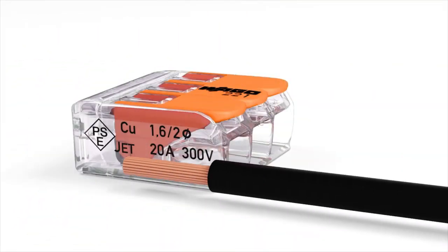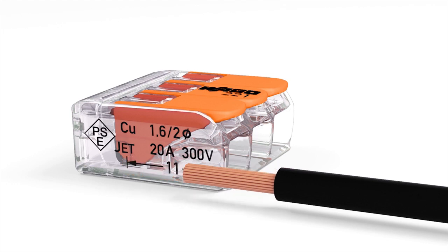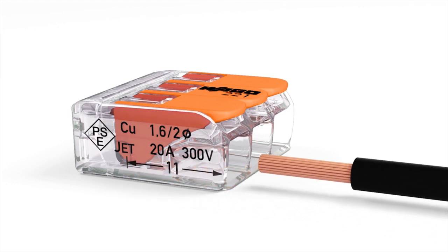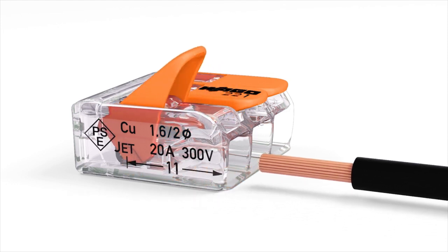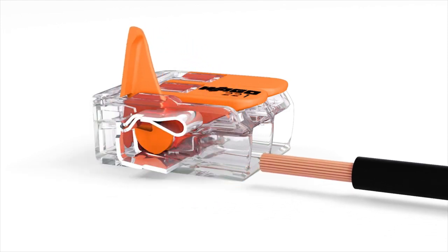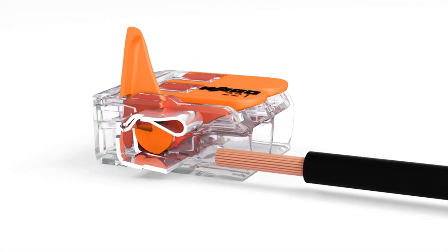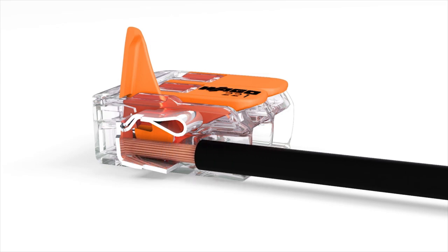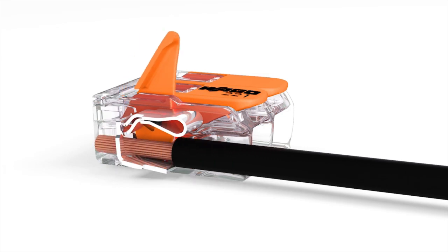Strip the conductor according to the strip length guide printed on the side of the connector housing. Open the clamping unit via the easy to use orange lever. Insert the stripped conductor, then lower the lever to close the clamp.